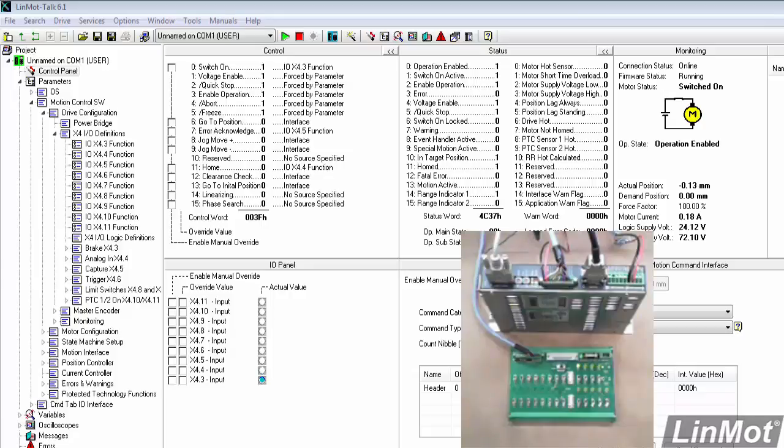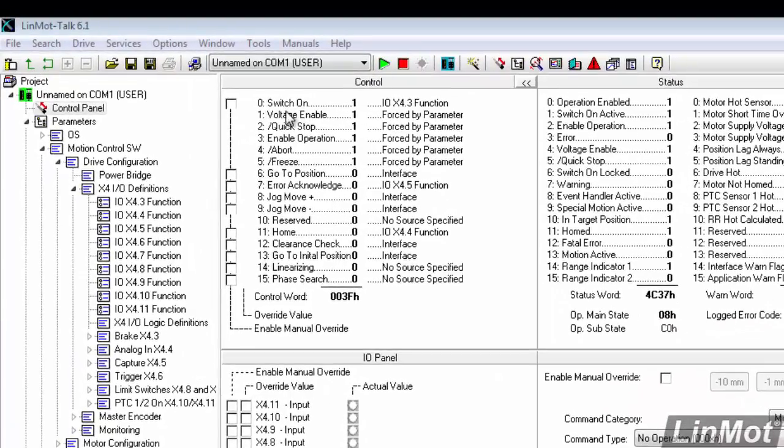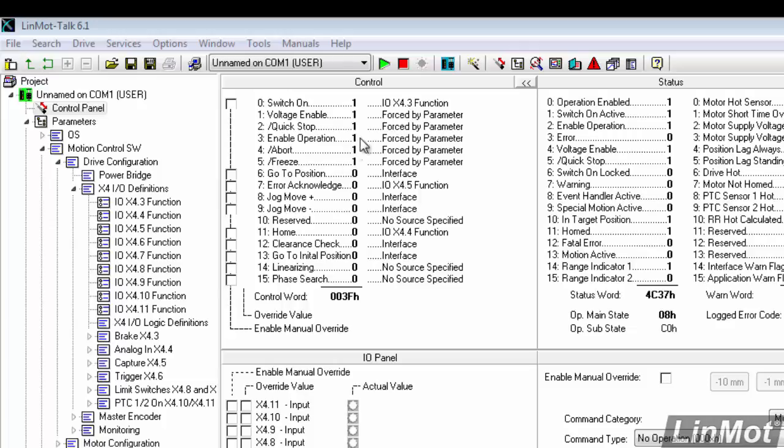So just to review, we've connected our switch-on bit of the control word to our X4 pin 3. We've connected our home bit to X4 connector pin 4, and we've connected our error-acknowledged bit to X4 connector pin 5.